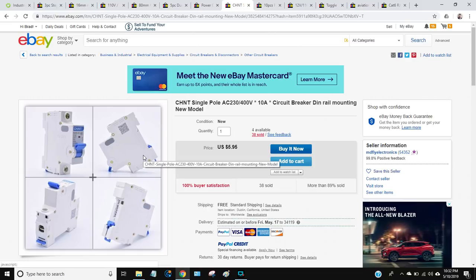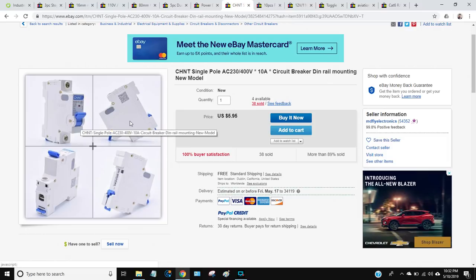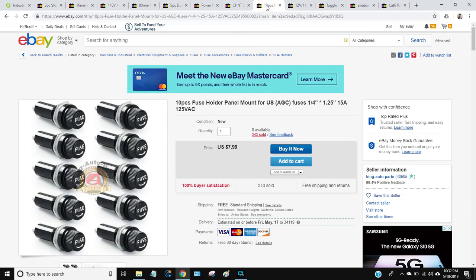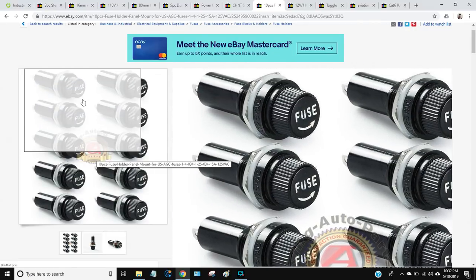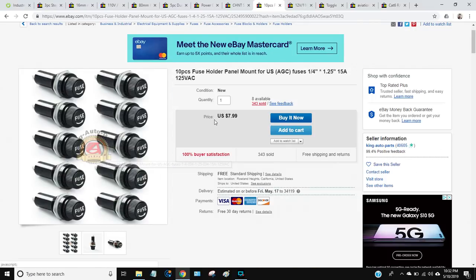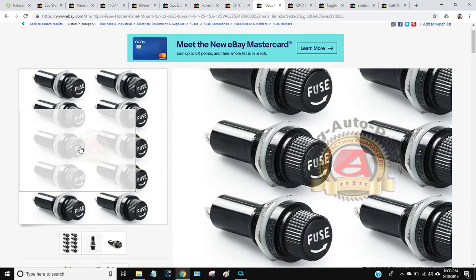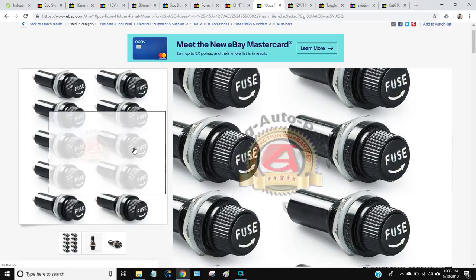Or a breaker - you're going to need some kind of circuit protection. I just pulled up an example here, this is a single pole 10 amp circuit breaker DIN rail mount. So this would literally mount right on your DIN rail and you could use this as a circuit breaker inside your control box. If you're not into circuit breakers, you can go with a fuse holder. These are relatively inexpensive, they use quarter inch fuses, you can get different size fuses. Gives you some flexibility, another option if you don't want to use circuit breakers.